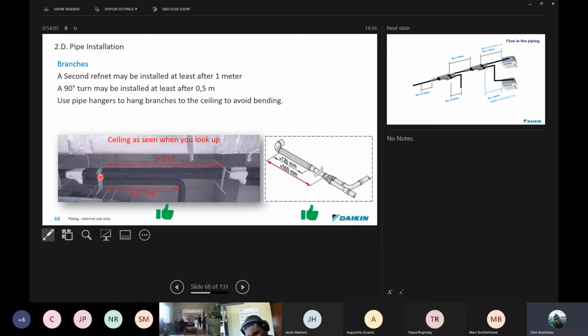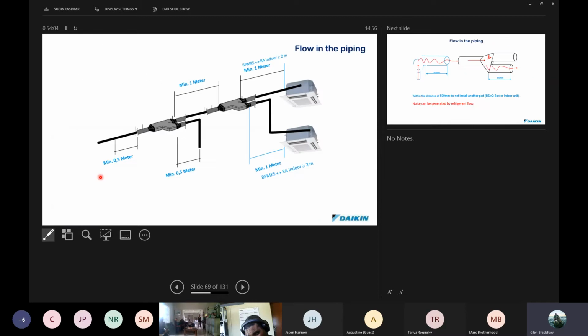Each joint must be supported by a hanger if you choose to use this type of hanger and not cable tray. What does that look like in schematic form? Basically, this is what we're looking at over here. Any time on the indoor units, we must have a minimum of 500 millimeters of straight piping going in, a minimum of 1 meter between RefNets, and a minimum of 500 millimeters of piping coming out. If you've got to a unit, minimum 1 meter of piping, so you cannot come out and go straight into a unit. You need at least 1 meter of piping before you go into that unit.